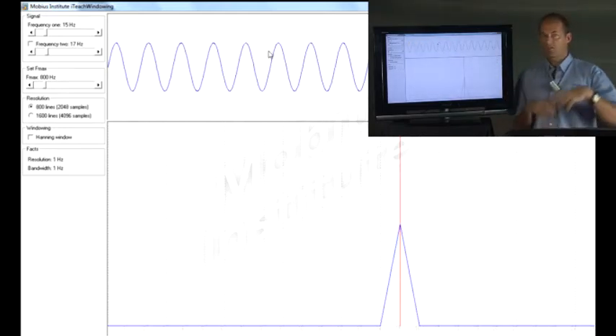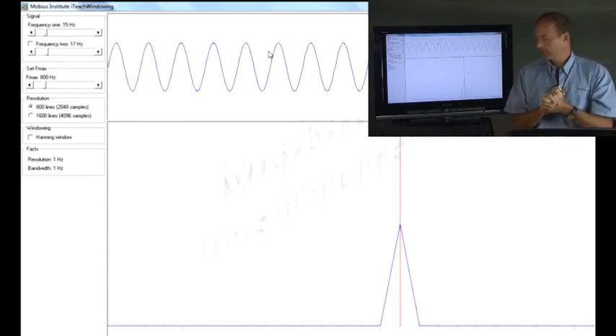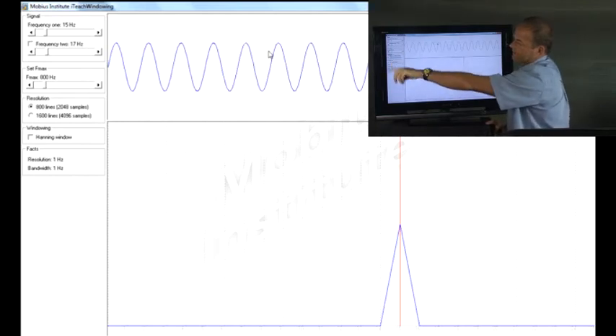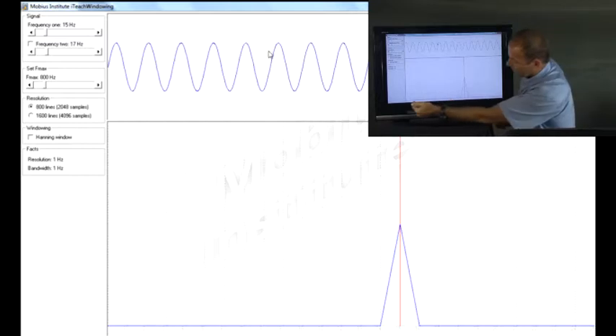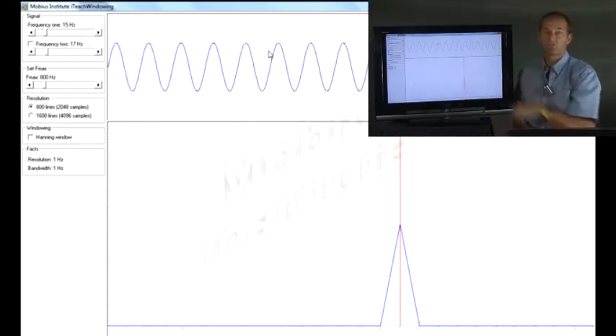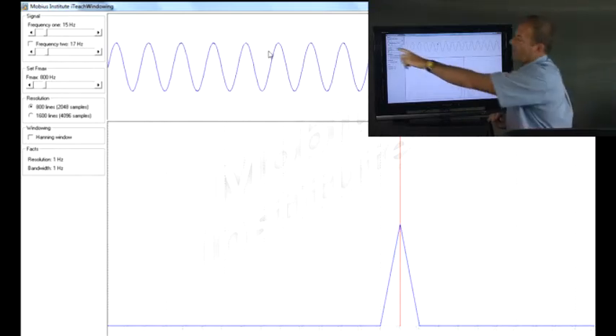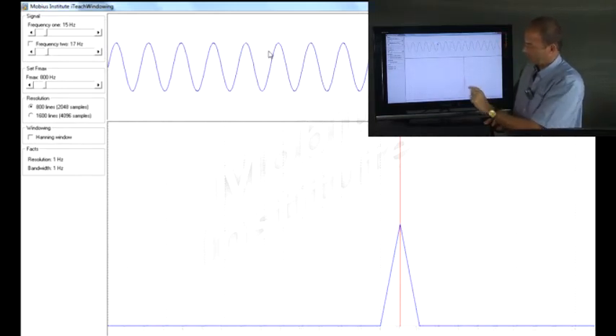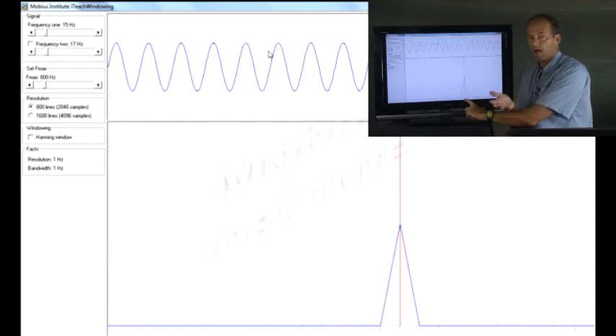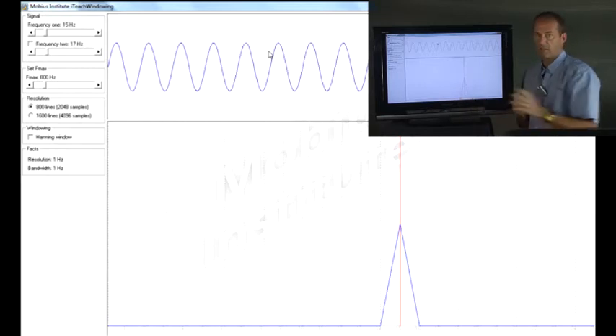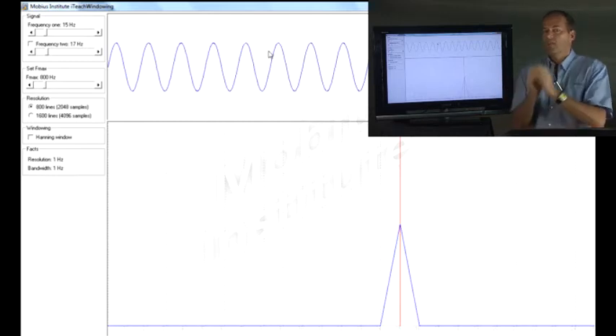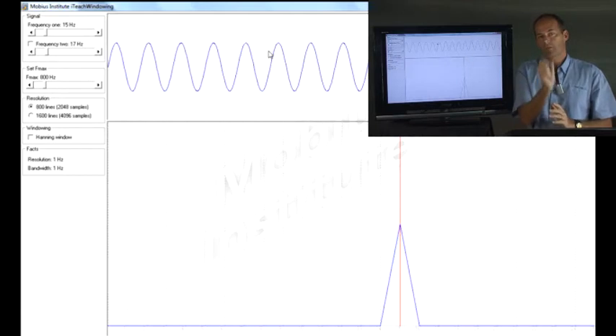What we've got here is a source of vibration, just an individual frequency. And what we're looking at down here is a real close-up of a peak in a spectrum. So I happen to have 800 lines and 800 hertz as my f max. And I've zoomed in from 0 hertz to 25 hertz. And each one of these little faint lines that you can see there is a frequency in the spectrum. So I am generating 15 hertz, so I get a nice sharp peak right at the 15th line in the spectrum or 15th bin. And there's no vibration at 14, no vibration at 16, so that's great. This is the perfect case where the frequency I'm generating happens to be exactly the same as one of the bins in the spectrum.